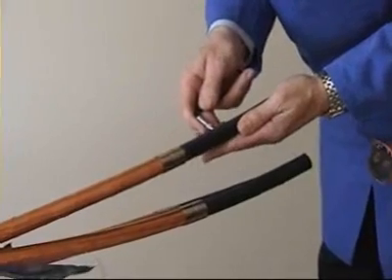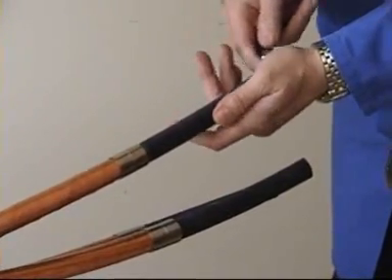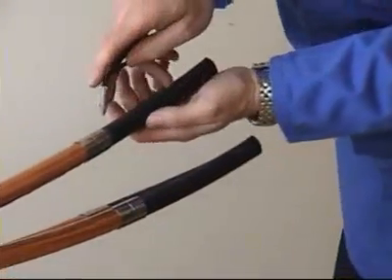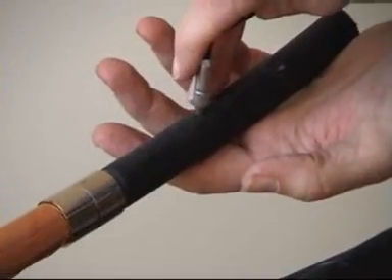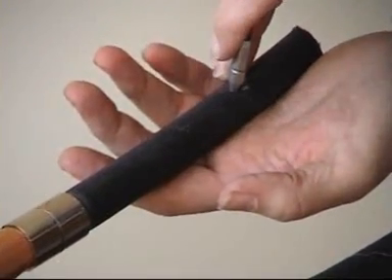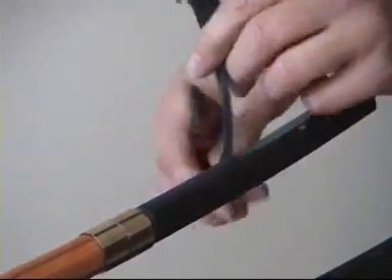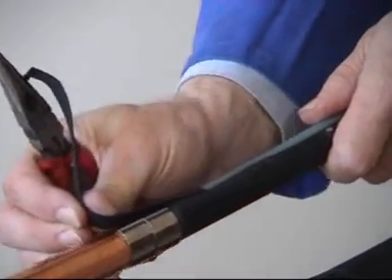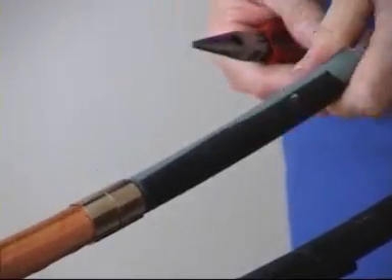Use a semi-conductive scoring tool and score the cores longitudinally, as shown. Make sure the tool is set to the right depth, so as not to score the primary insulation. Peel back the semi-conductive layer, which should snap off at the screen cut.